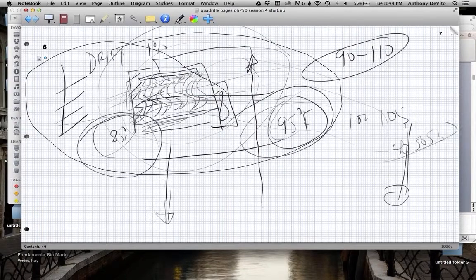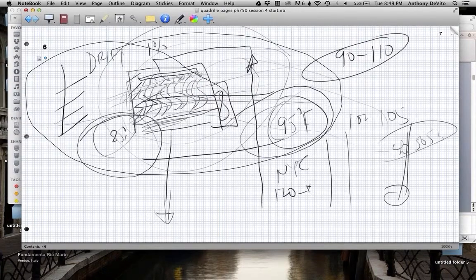So now, cold water doesn't seem like a great place for this to grow. What temperature do you think the hot water is coming out of your spigot, the hottest it gets? Well, the New York City Department of Health regulates that, right? They recommend that you keep it between 120 and 140. Not a great growth range for Legionella. That's one of the reasons they tell you to keep it at 120. Why do they keep it not above 140? Well, you don't have time to put your hand under there, 140 degrees. You won't have time to pull your hand away. You'll get burned, just testing the water, right?